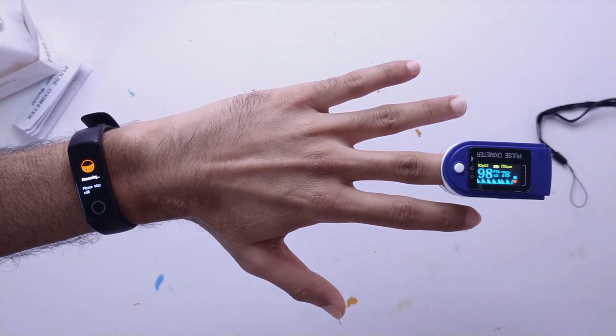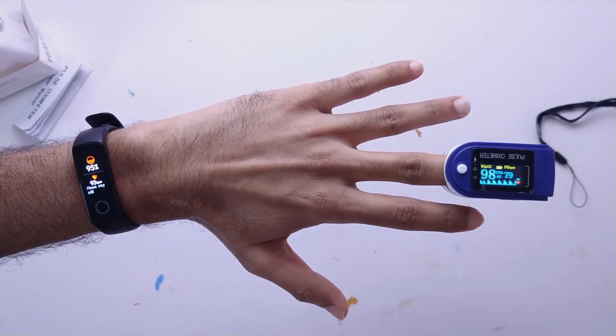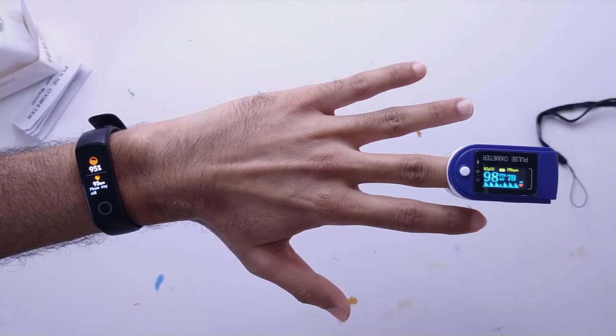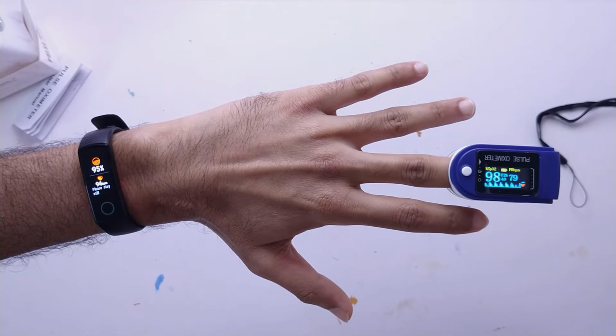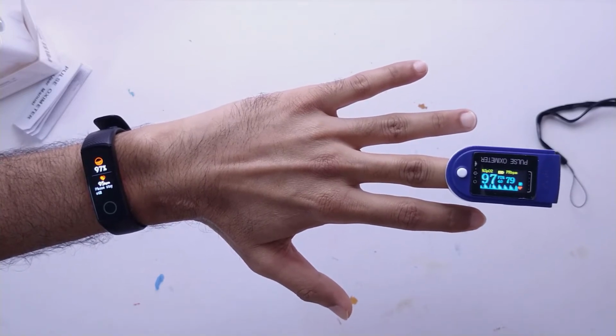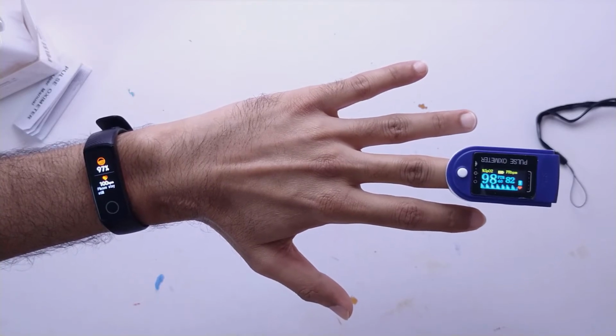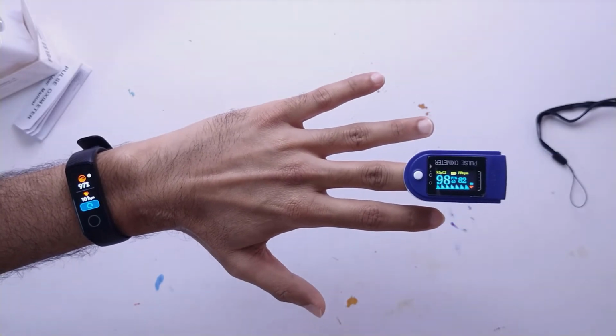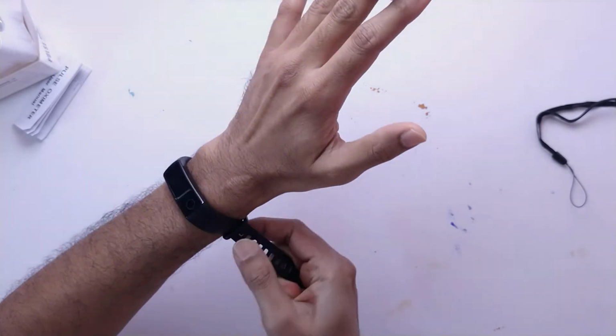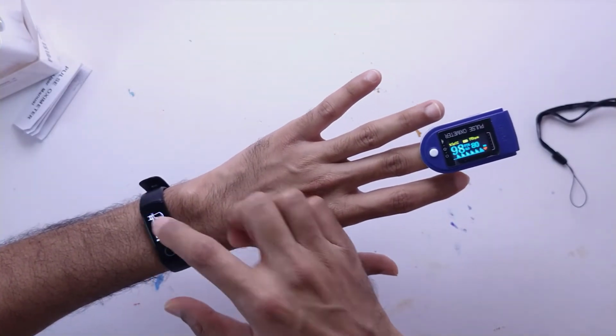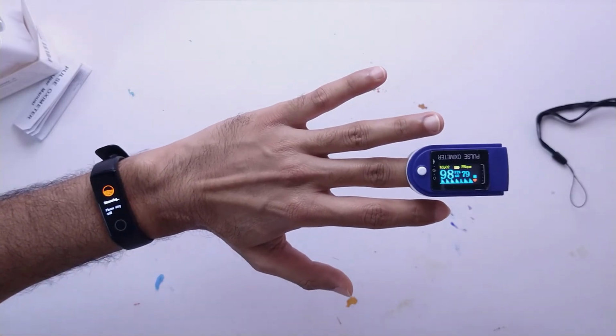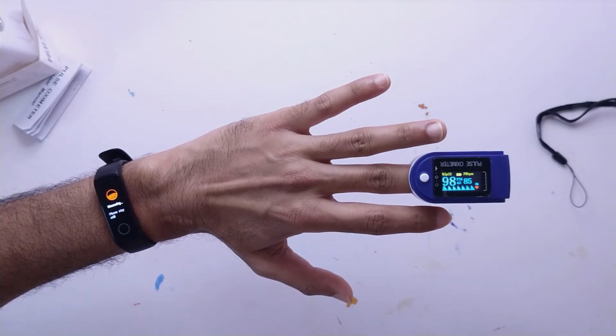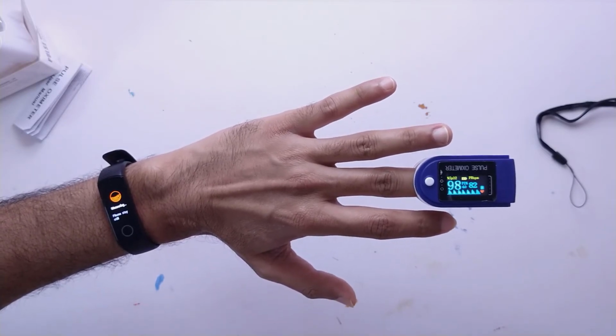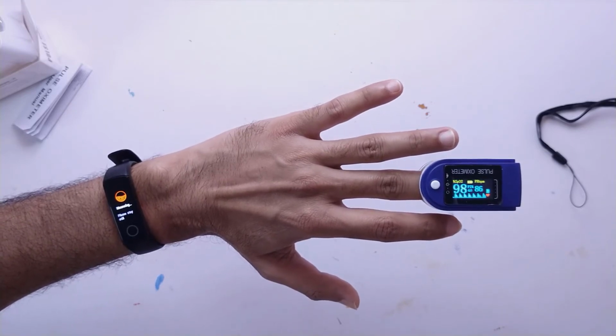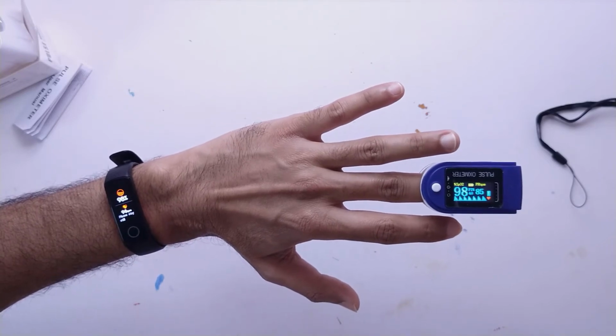And my Honor Band 5 is working and it is showing 95%. Since I have hair on my hand, it shows a lower reading, and if I keep the wristband on for a long time, then it gives a fair result, otherwise it gives a lower result. It is showing 97% and it's gone. I have to tighten the strap. It works only with a tight strap, otherwise if you put it loose, it won't work. The pulse oximeter is showing 98% with 84 beat rate, and my Huawei Honor Band 5 is working. It takes some time for the Band 5 to give the result. It actually computes it inside, I guess.